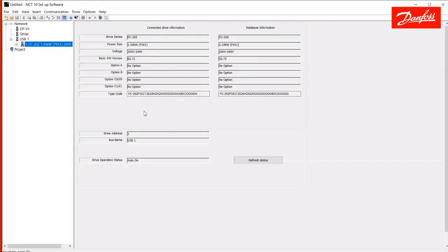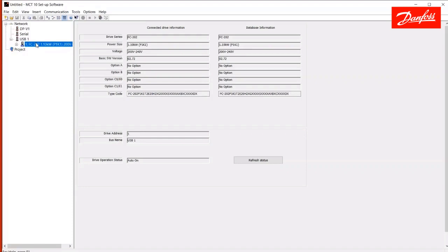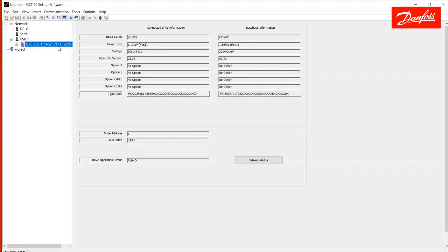There may be occasions where you plug the drive into the laptop and it appears on the USB side. However, instead of the drive being identified, you see a circle, a red circle with a cross through it here. And that means that the drive, or I'm sorry, the software sees a connected drive, but it does not have the database for it. When that happens, you'll see a button down here that'll say download drive database. Clicking that button will allow the software to upload that database so it then will understand that drive. After that process is done, everything will look normal like this.